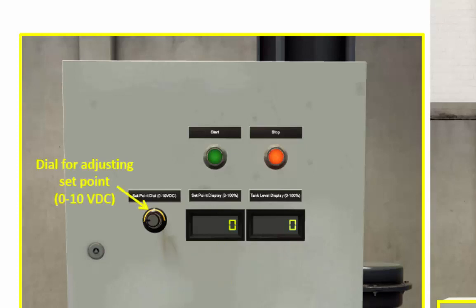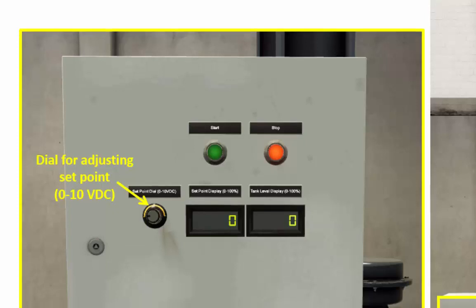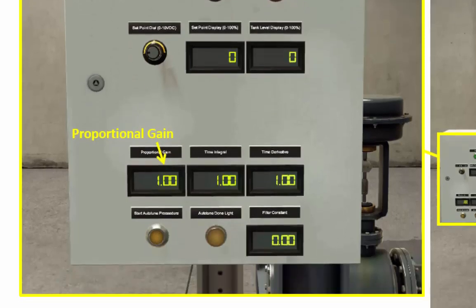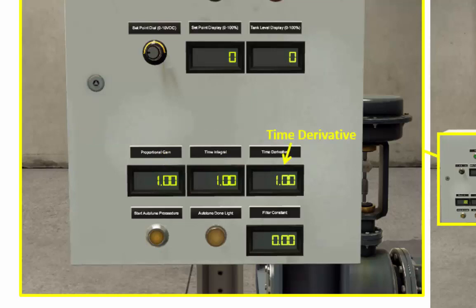You should program your PLC so that this dial adjusts the fill level. This is a 0-10 volt DC dial, and the input from that should be scaled to a 0-100% full set point. These displays down here should show the gain values — this one should show the proportional gain, this one should show the time integral, and this one should show the time derivative.